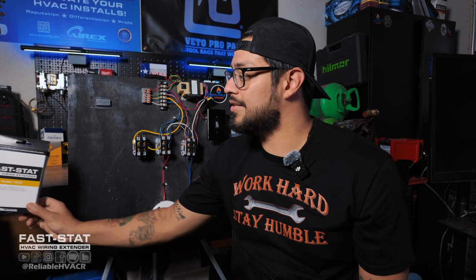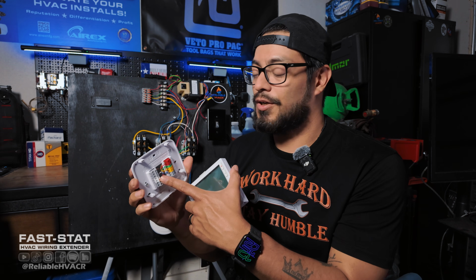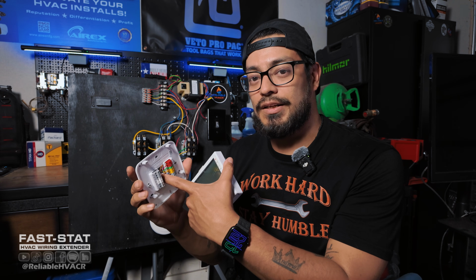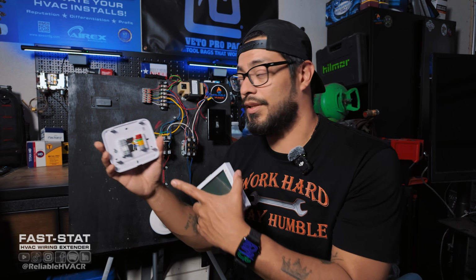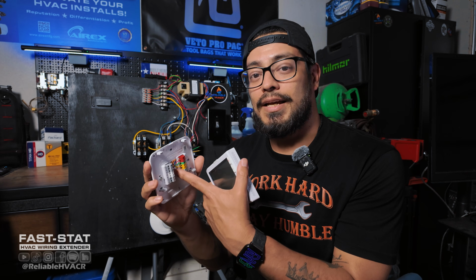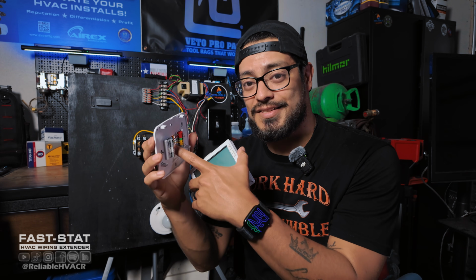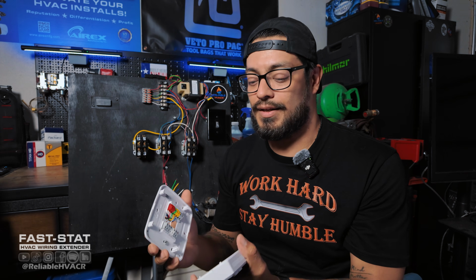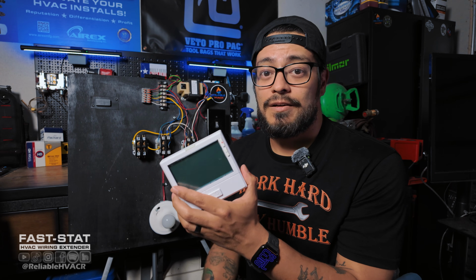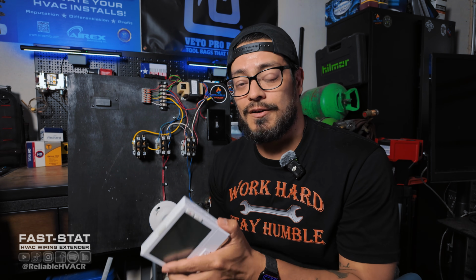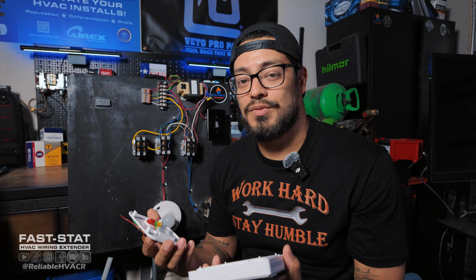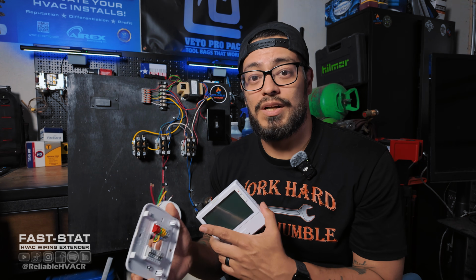They do make one of these that only gives you one extra wire to use for common. In that instance, you would hook it up here to your common, throw it in and wire it up to the diagram. We'll get into that and leave it. There's a little dongle that stays in the wall there. It doesn't generate a lot of heat or anything like that. And maybe they want to upgrade to a Nest thermostat. That would be a great scenario for using the Fast-Stat common maker. You get a solution when you don't have enough wiring.